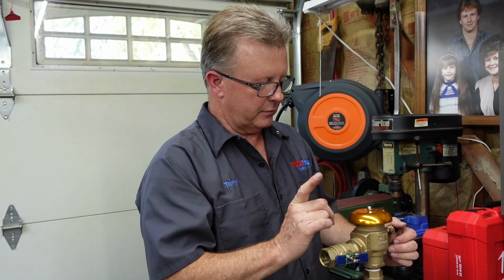At that point you can go ahead and work on this device. I recommend that through one of these test ports right here, you use a screwdriver and open that up 90 degrees right there, and that will take the pressure off of this device, and let some water out so you don't get poof in your face when you go to take it apart.